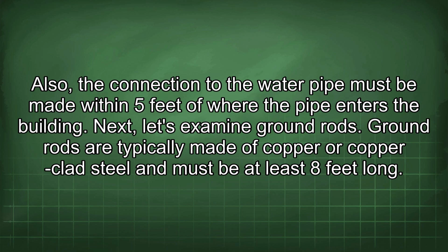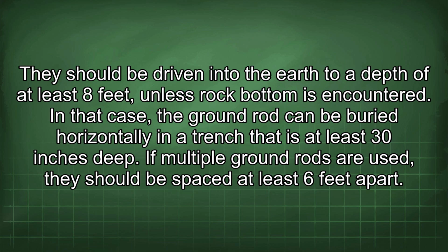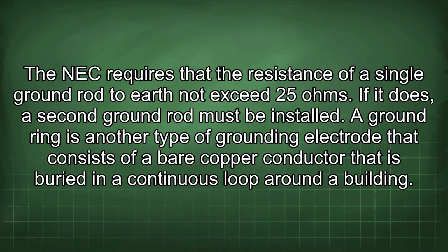Next, let's examine ground rods. Ground rods are typically made of copper or copper-clad steel and must be at least 8 feet long. They should be driven into the earth to a depth of at least 8 feet unless rock bottom is encountered. In that case, the ground rod can be buried horizontally in a trench that is at least 30 inches deep. If multiple ground rods are used, they should be spaced at least 6 feet apart. The NEC requires that the resistance of a single ground rod to earth not exceed 25 ohms. If it does, a second ground rod must be installed.